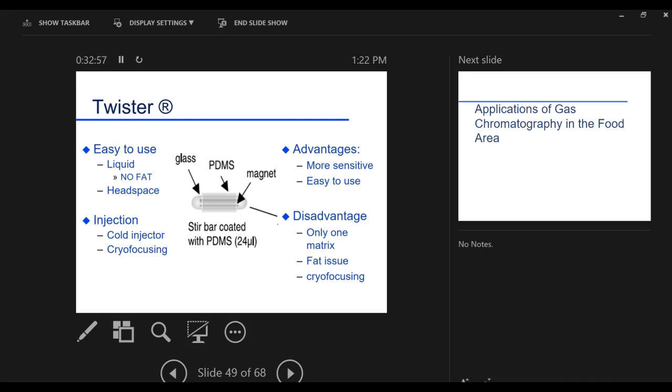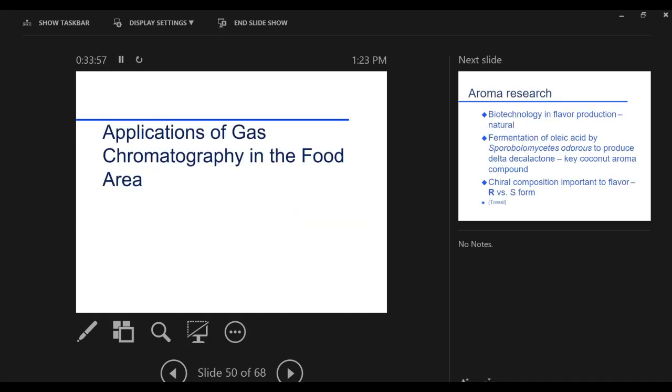The idea of dropping this in the injection port, well, we do that. But then it kind of takes a while to warm up. And while it's warming up, some things are being eluted off the column. Some things aren't being eluted off that column. And so we can end up with peaks that are kind of broad. So that's not convenient for us. So oftentimes what we have to do is we have to put this in the heated area, have a device that is cooled with liquid nitrogen. So everything that comes off it goes into a liquid nitrogen cooled section. So we basically freeze everything right here. After this has had enough time to unload onto the cold trap, that gets heated in a matter of one or two seconds up to 200 degrees centigrade. And then this goes into our column. So oftentimes we really need to focus everything. So desorbing is difficult. The idea of slowly desorbing, trapping it again, and then analysis is the best way to go.